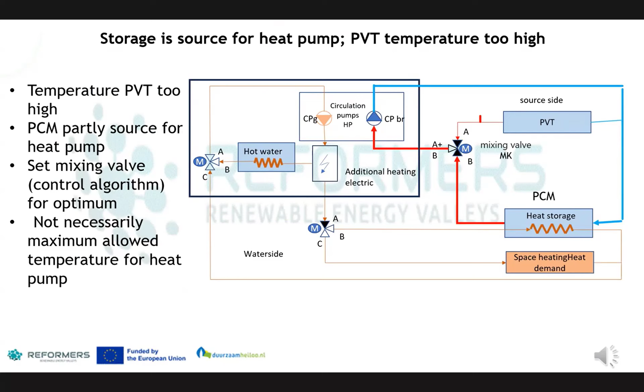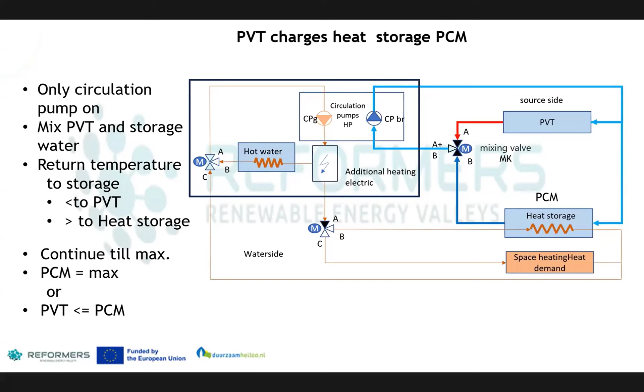The PCM storage can be reloaded also later. If the temperature of the PVT is high, when in daytime the temperature is high with sun on the panels and there is no heat demand, the PCM tank can be charged if the circulation pump of the heat pump can be controlled separately. Otherwise, an extra circulation pump is needed. By the control program, then the hot and relatively cold flows from the PCM tank are mixed by the mixing valve. Then, the return temperature is higher than the temperature of the PCM and lower than T PVT. This continues until the temperature of the PCM tank reaches the maximum allowable temperature for the heat pump, or until the temperature of the PVT is equal to or lower than that of the PCM tank.